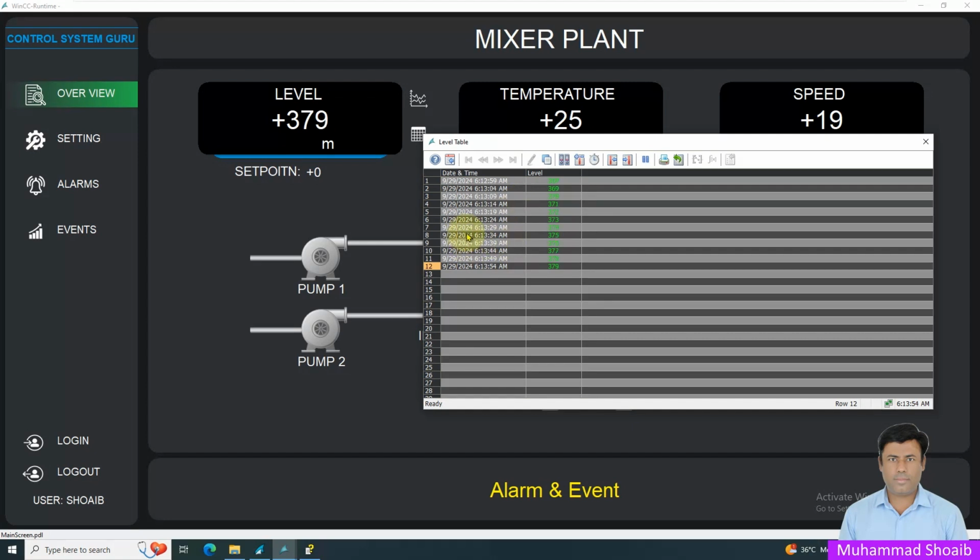In the previous tutorial, we saw that we were logging our data with a 1 second interval. Then we wanted to optimize data and reduce the data consumption, so we increased the timer to 5 seconds. Now with hysteresis, as I explained before, only once the specific amount of data changes will the data be stored inside our database. So let's see how we can configure it.